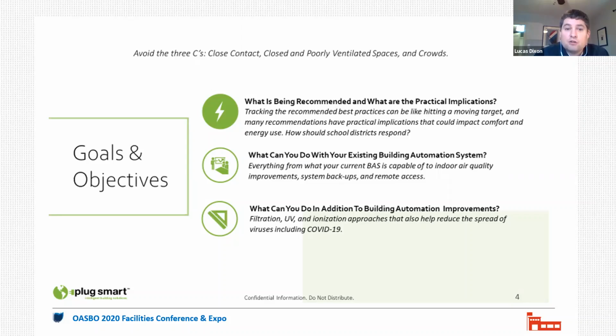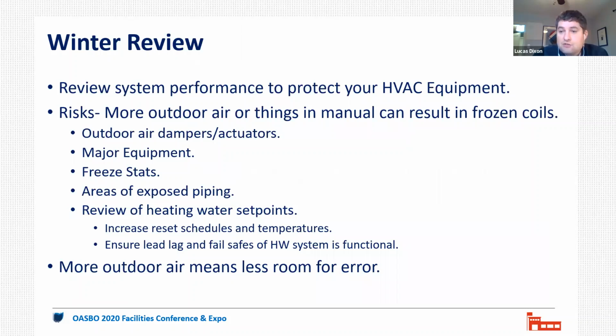We had to adapt our control schemes. But now, coming into winter and approaching December, January, and February, when we'll see our coldest temperatures, we need to protect our infrastructure differently. We've worked to bring in as much outdoor air as possible, but now we have to take the approach of do no harm to our mechanical systems. We have to make sure we're protected and not creating more problems while maintaining as much outdoor air as possible.